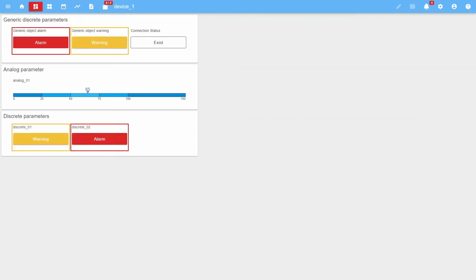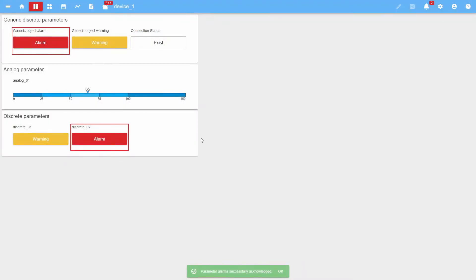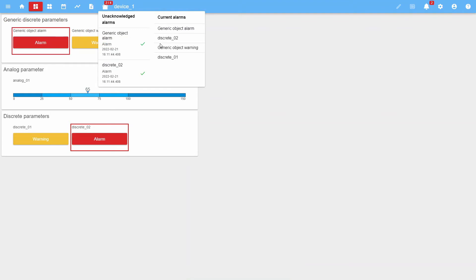As we can see, both discrete parameter widgets and generic parameter widgets have taken the active state. The widget frame indicates that the alarm has not been acknowledged. When we acknowledge the notification, the frame disappears. Let's pay attention to the alarm counter — they are two out of four, meaning that at the moment two active alarms are unacknowledged out of four active alarms.